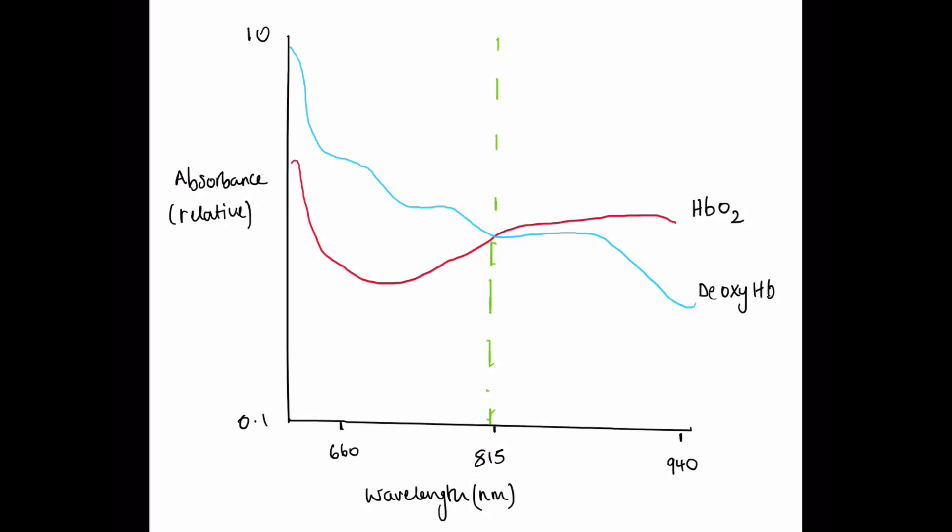What we can see is that deoxygenated hemoglobin absorbs more red light and oxygenated hemoglobin absorbs more infrared light. There is an isosbestic point at around 815 nanometers and this represents the point at which both types of hemoglobin absorb the same amount of light.